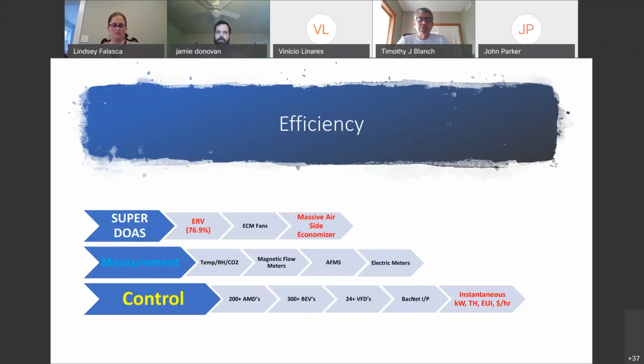Next, yeah. So the super DOAS was made possible by 76.9% energy recovery enthalpy wheels. Also, EC fans. We had some of the first high static ones in the industry, which really do save a lot of energy. This is an advantage of air over hydronics these days. We have no advances in hydronic efficiency on pumping. Essentially, the motors are the same. AC motors with drives are the same efficiency they've been for many decades. So the drives have helped us save energy, but not the motors and not the pumps. But electronically commutated motors, introduced mainly now for fans, are a large advance in energy efficiency, making air movement much more competitive versus hydronic energy transfer that we have largely relied on in the past.